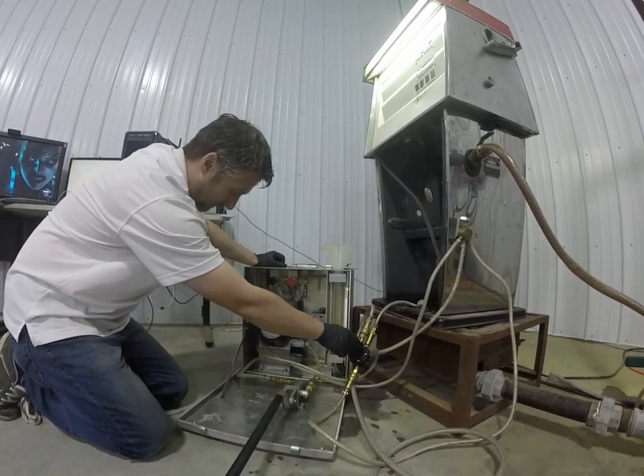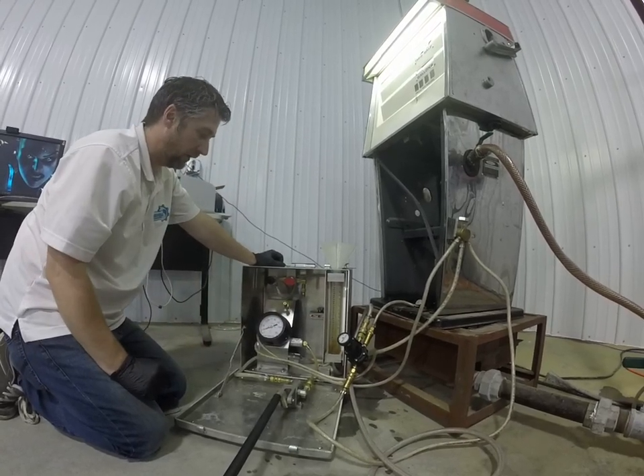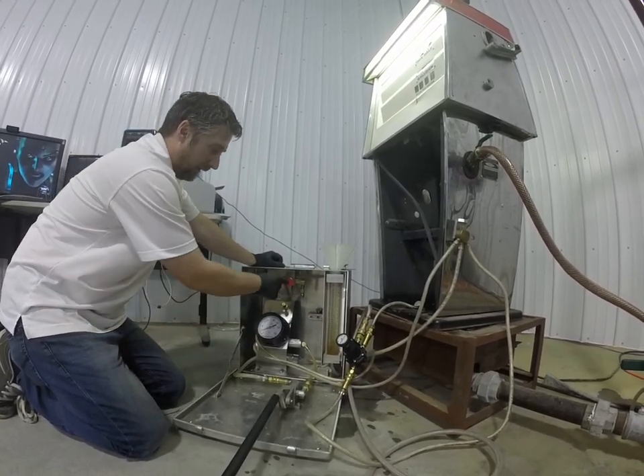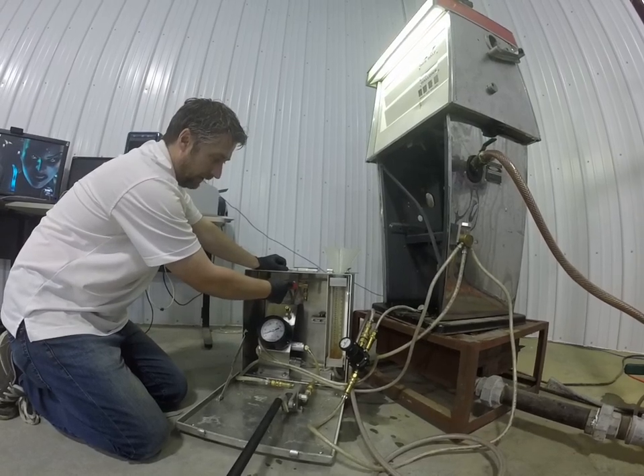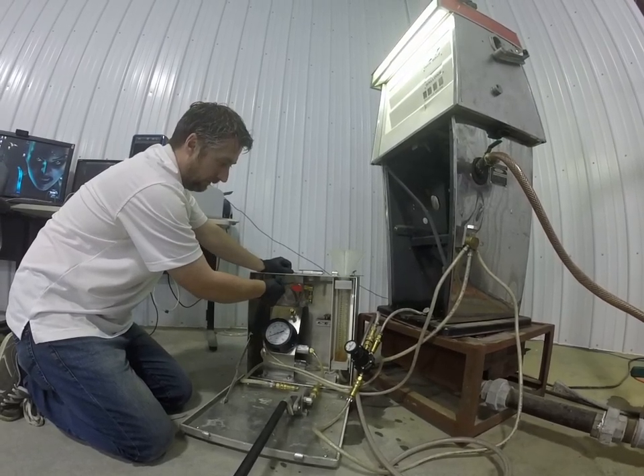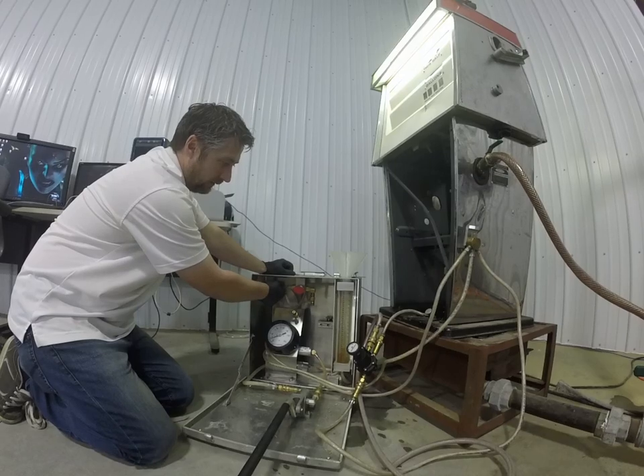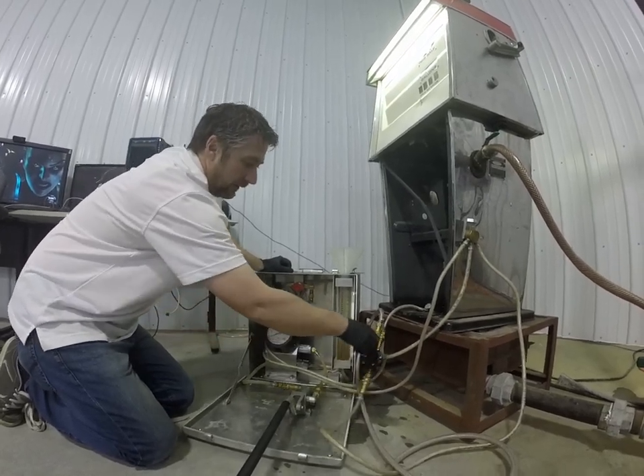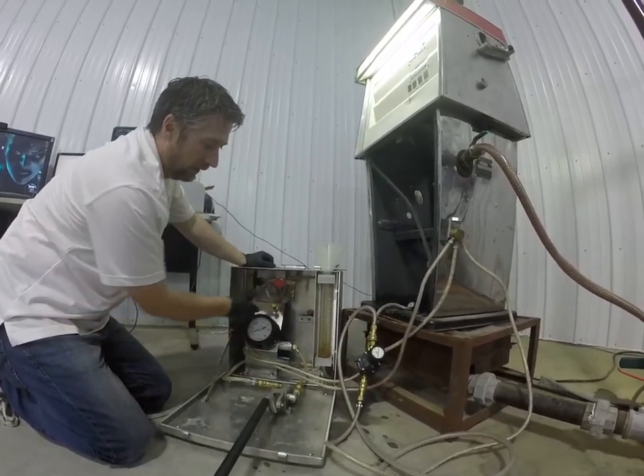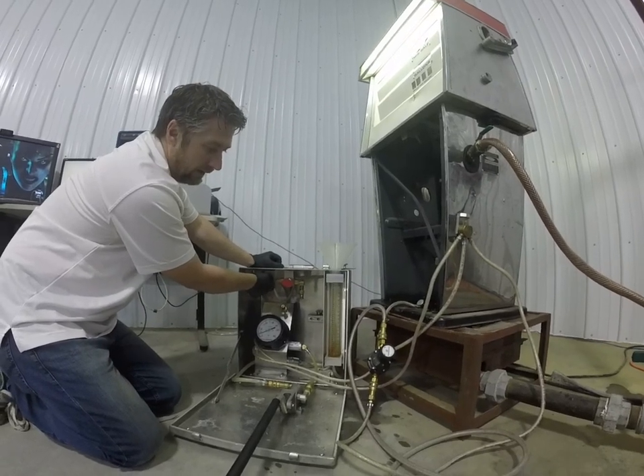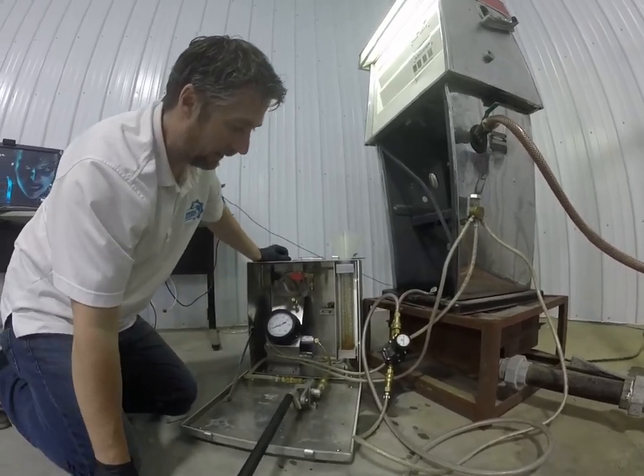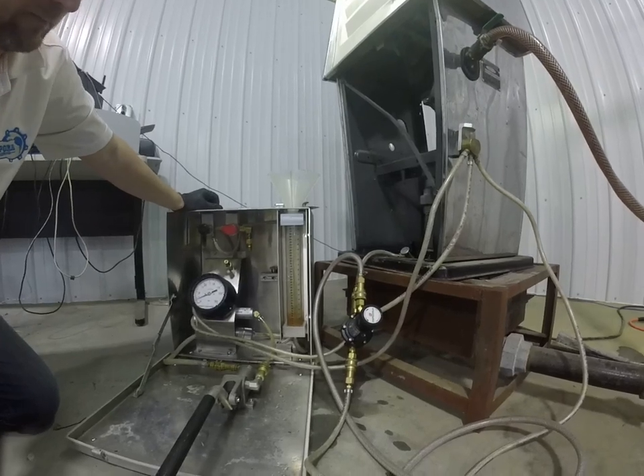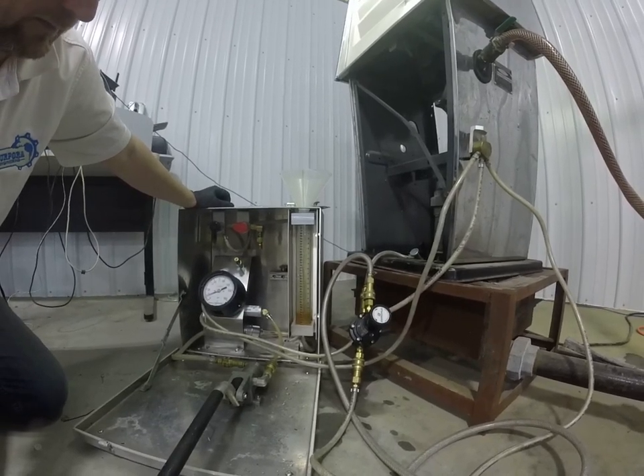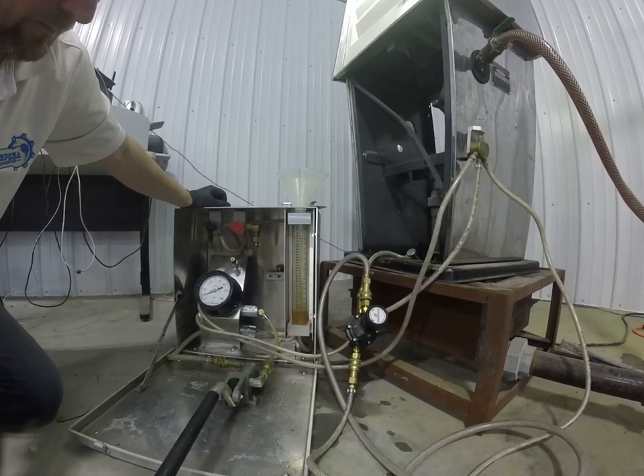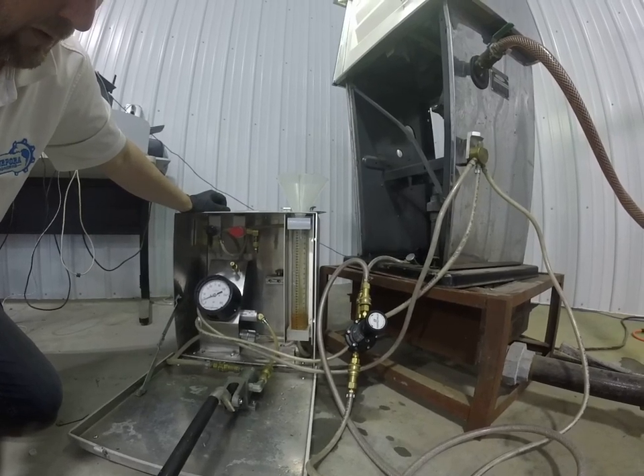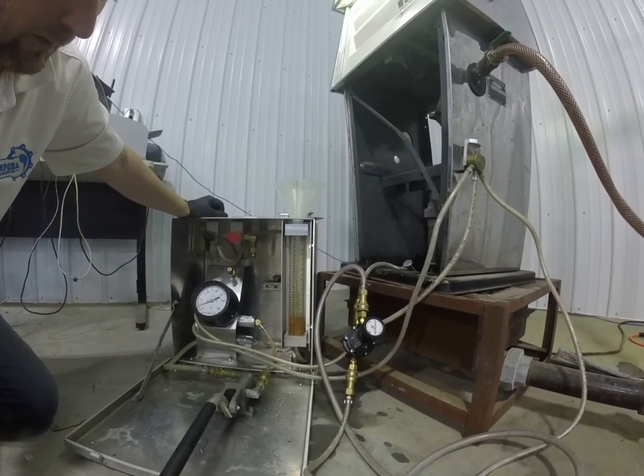So once we have the 10 psi set, we're able to start regulating the flow of liquid into the burette. As I said, with the hokey valve, with the red valve turned towards the flow of the burette, we can start letting liquid enter the burette. We're going to control this leak so that liquid flows into the burette at approximately 15.7 mils for every 5 seconds. So we're just going to count 1, 2, 3, 4, 5.